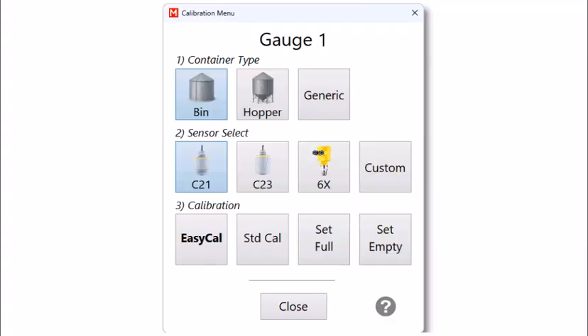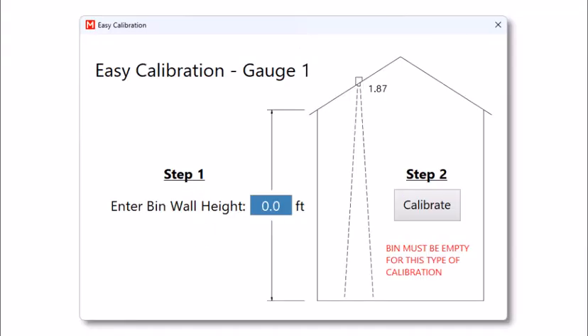The Easy Calibration option is going to be the quickest and most accurate for the standard bin. We'll start with that one. There are a few requirements that must be met to perform an easy calibration. First, the bin must be empty. Second, the sensor must be mounted in an MTEC bracket on a 30-degree roof pitch. Third, the sensor must be mounted halfway between the edge of the bin and the tip of the roof. And fourth, the bin must not be a hopper style. If all of these things are true, then we can proceed with the easy calibration.